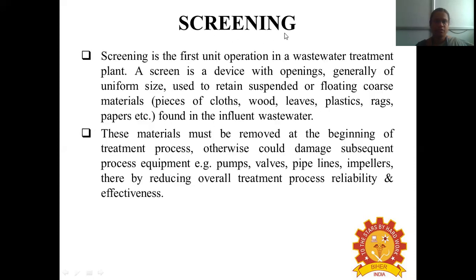The first process or preliminary process of wastewater treatment is screening. A screen is the first unit operation in a wastewater treatment plant. A screen is a device with openings, generally of uniform size, used to retain suspended or floating materials like cloth pieces, wood, leaves, plastics, rags, and papers found in the influent wastewater from different industries. These materials must be removed at the beginning of the treatment process.